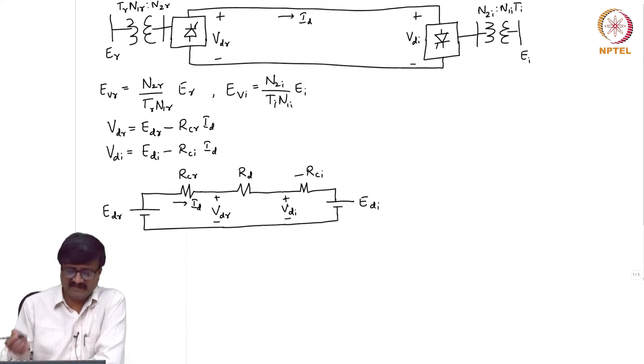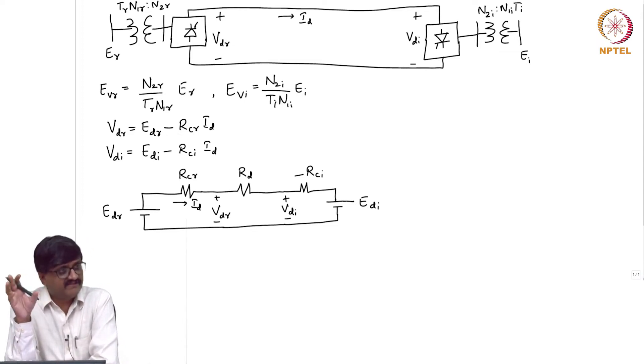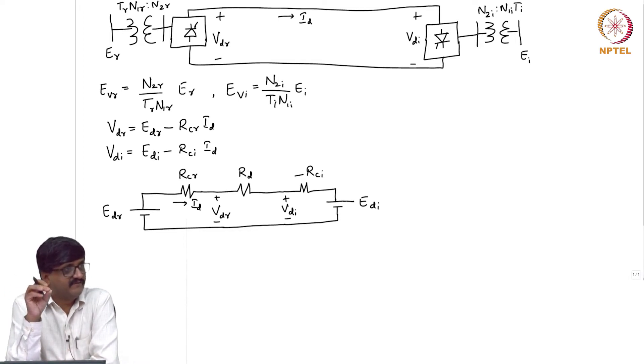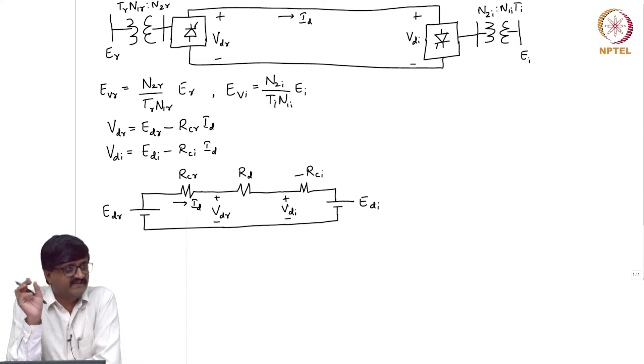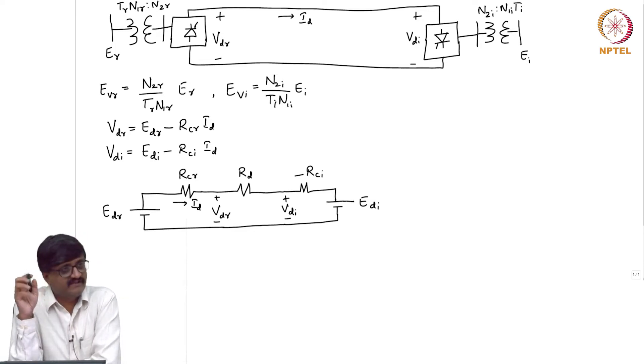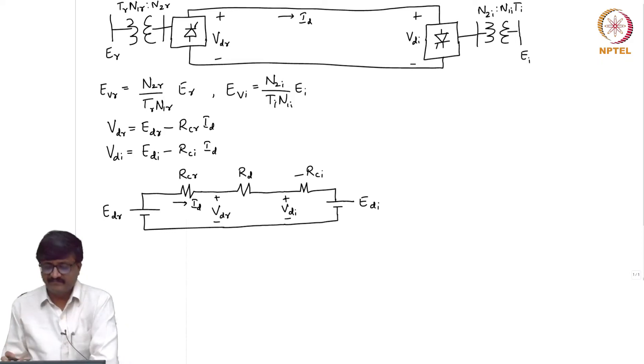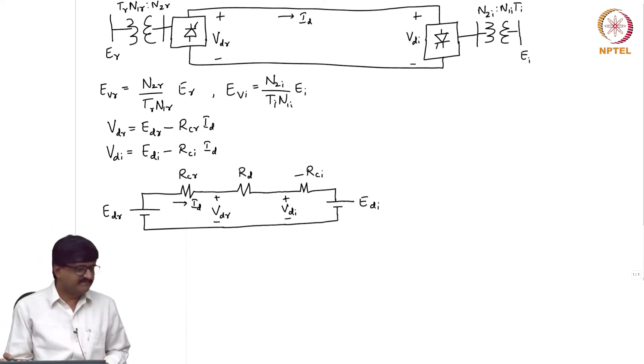Please note that R_CR and R_CI are not actually physical resistances — there is no loss corresponding to them. They arise from leakage inductances, as seen in the expressions for R_CR and R_CI. So one should not assume there is a loss due to R_CR or a generation due to minus R_CI. The only actual loss is due to R_D, which is the physical resistance of the transmission line.